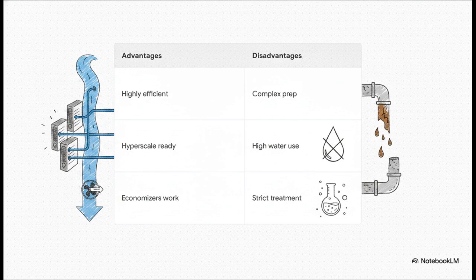These systems are highly complex to maintain. They require massive amounts of water consumption because of that evaporation process, and the water quality is absolutely critical. Poor water treatment can lead to scaling, corrosion, and fouling, which means you need constant, strict monitoring.